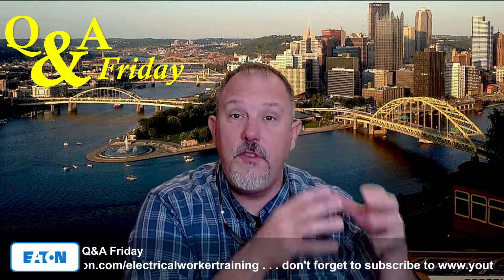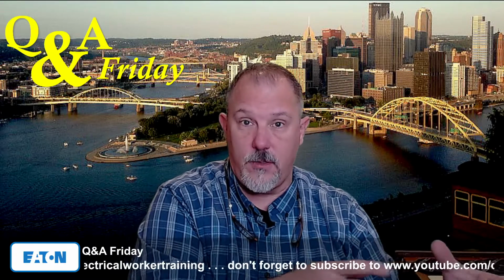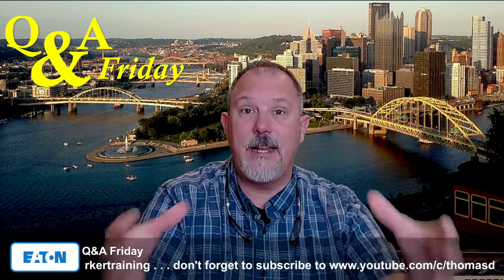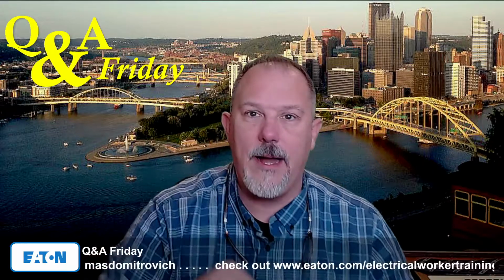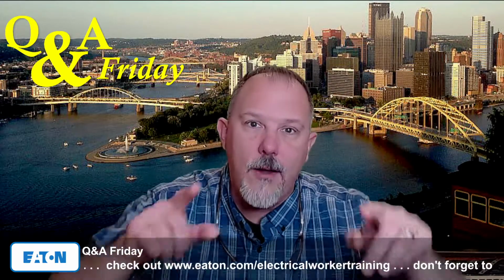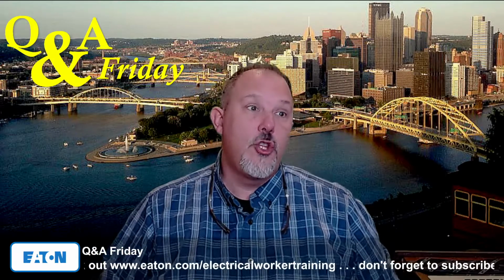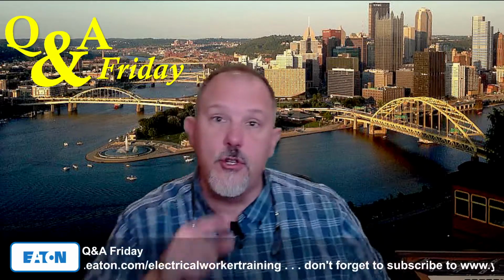I can do things as a manufacturer of an assembly that you would not be permitted to do in the field. A good example of that is the types of wire that we permit inside of a piece of equipment. And you may say, how could they use that wire with that overcurrent protective device routed where it's at? There's no protection, there's no conduit, there's no raceway.